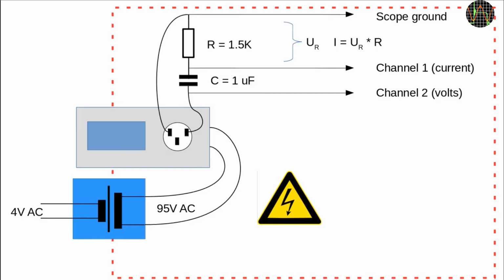After I succeeded in testing the frequency display, I wondered if I could verify the power factor too. This is much harder. In the end, I used this setup. As before, the blue transformer is producing the AC voltage going into the power meter. I need to go to almost 100 volts to get enough current to flow, which makes this quite dangerous, so if you try this, you do so at your own risk. Basically everything in the red dotted box, including your scope, is at that high voltage.